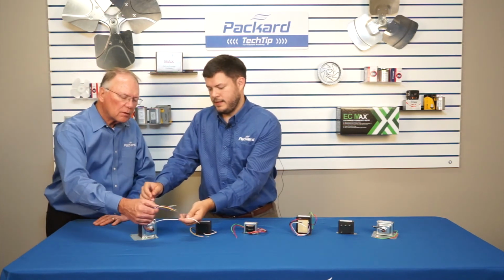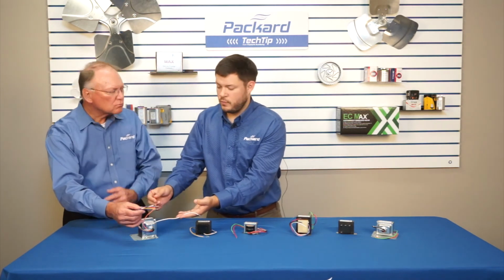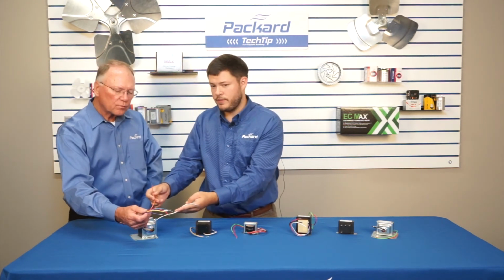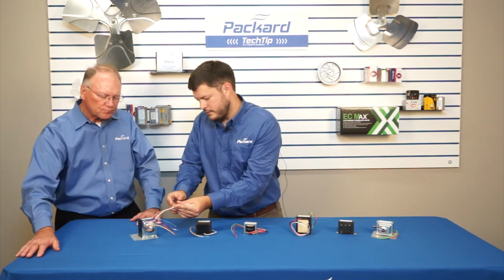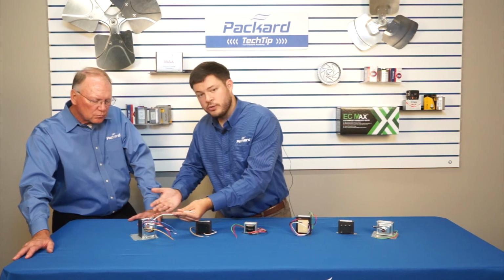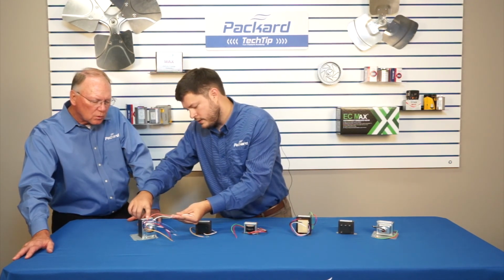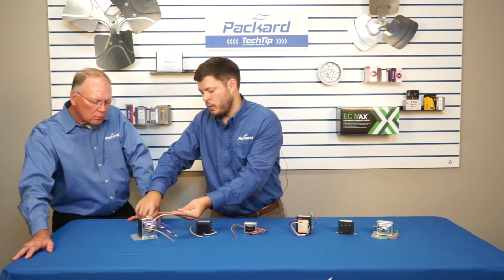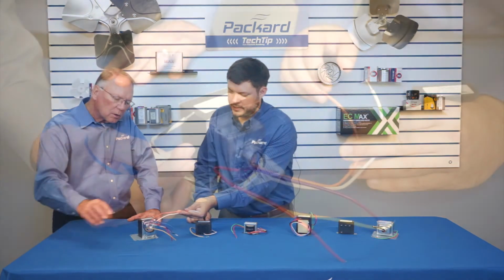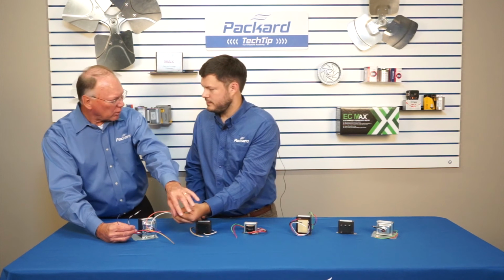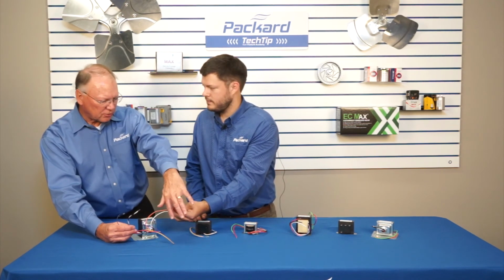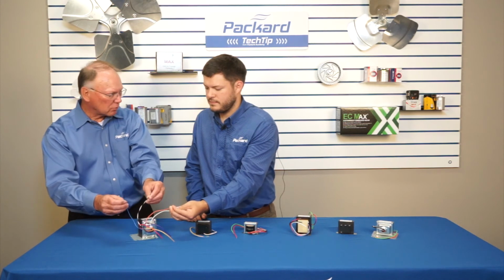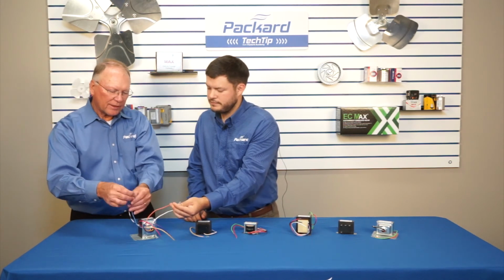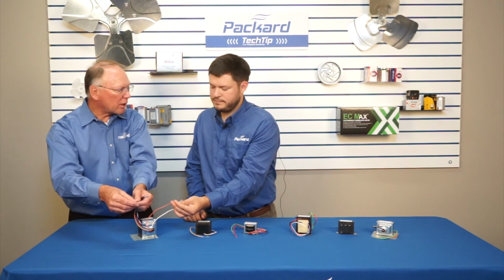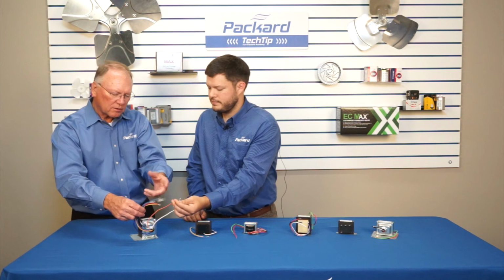How would you do that? A wire nut's a great way to do it. Any way to cap off that wire so it can't touch anything. And now on your secondary side, if you need 120 volts, you need to pick out the white slash black wire as well as the blue, which is your common on your secondary side. So when I apply 240 volts to my primary, I get 120 volts out of my secondary. That is correct. And then I would put wire nuts on the others to protect those. Absolutely, yes.